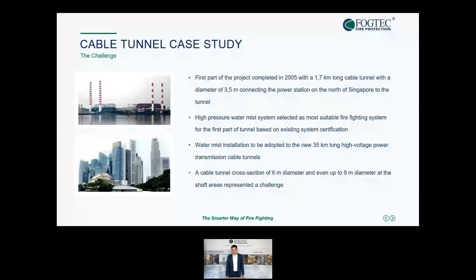This was jointly developed with the end client and the fire consultant, where we had two topics: the protection of the cables and the cable troughs, and additionally the service vehicle in the center of the tunnel, which needs all-time free accessibility into the tunnel. It's also important that in case of change of cables and cable troughs, all these must be freely accessible. So it was a very clear and tough request to have as little interference by a firefighting system as possible.